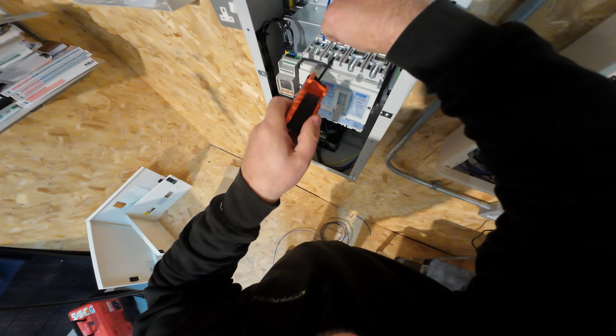So that RCD now has the main feed into it, and it then loops off from the output terminals off the top here and across to that metering kit to power everything in this bay. The reason I wanted to do that was to see what natural leakage was occurring, and if we've only got one circuit running through it, that's harder to do than if we've got multiple ones. We're going to grow and expand on this, and I'm going to change the setup in the entire academy to make better use of this, as you will see in the clip following this voiceover.